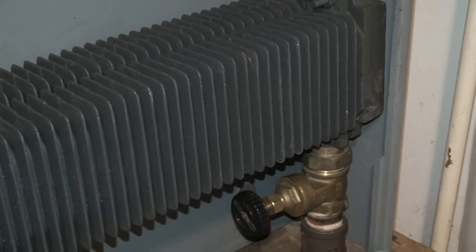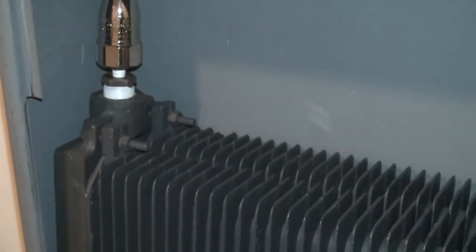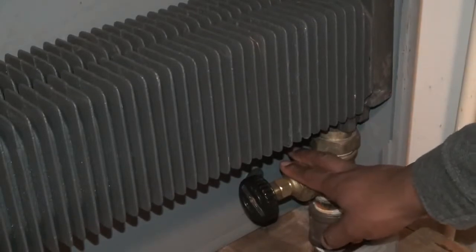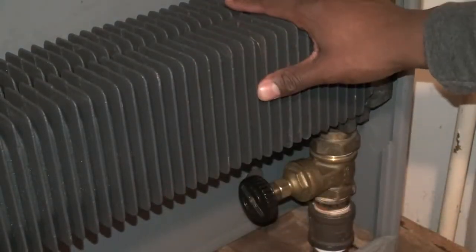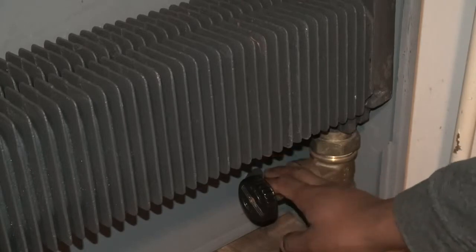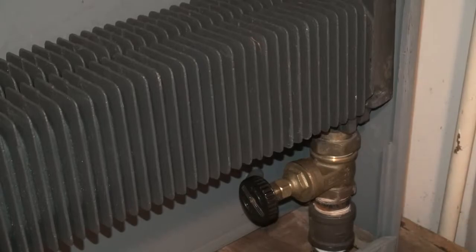I'm going to start the first half of this test, and like I said, this is going to consist of a Fluke meter and a stopwatch. It's going to consist of timing from the time that the steam enters the cutoff valve to the time that the steam gets to the air vent and that locks out. The second test is going to consist of the cutoff valve being shut down, and once again a stopwatch. And I'm going to let the boiler, the system build up pressure. I'm going to let it build up maximum pressure, and then I'm going to open it up once at the maximum pressure, and this is going to give us our reading. So that's how we're going to do this. So stay tuned for both tests.